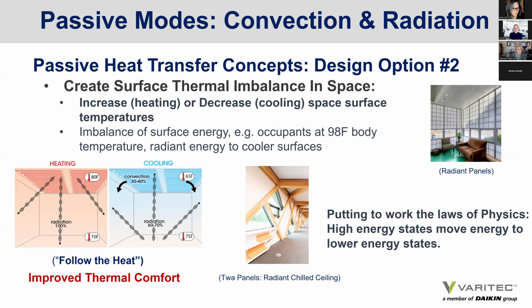Another passive mode of heat transfer is to use radiation by creating a thermal imbalance in surfaces of a space. If we cool or warm surfaces in a space, let radiation do the heat transfer work for you. By cooling a ceiling, any surface that has a higher temperature or energy level than the room set point condition will emit its radiant energy to the cooler surface. It occurs spontaneously and at the speed of light. So by using passive modes of heat transfer, we're allowing the laws of physics to go to work for us, as opposed to using mechanically driven systems that consume energy to move energy.